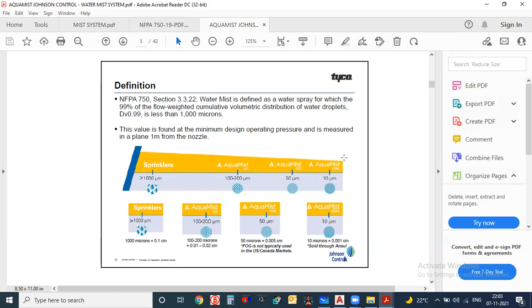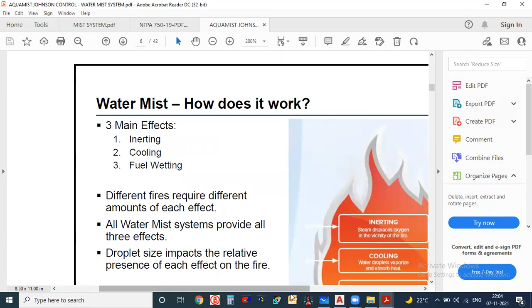How does it work? Three main effects: inerting, cooling, and fuel wetting. First, inerting, where the system displaces oxygen in the vicinity of the fire. Second, water droplets vaporize and absorb radiant heat. Third, water droplets wet fuel sources, preventing the fire from propagating.